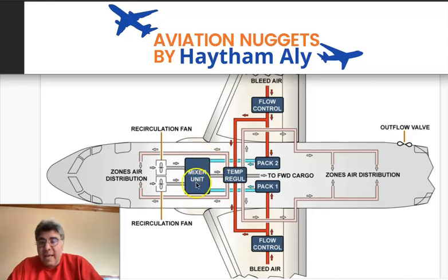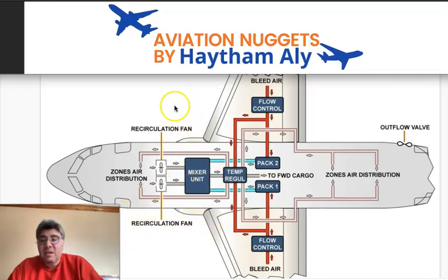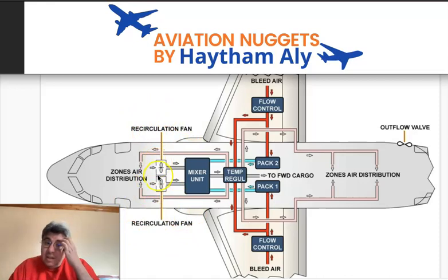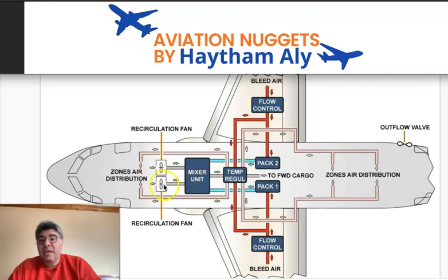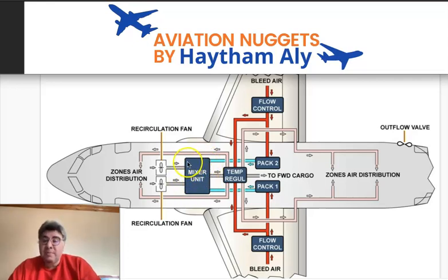What is the function of the mixer unit? The mixer unit is used for fuel saving and cost saving. Thanks to the mixer unit, we can mix some air from the cabin using the two recirculation fans, which collect air from the cockpit and cabin. The mixer unit mixes this recirculated air with fresh air coming from the packs, so the air conditioning system does not depend solely on the packs.